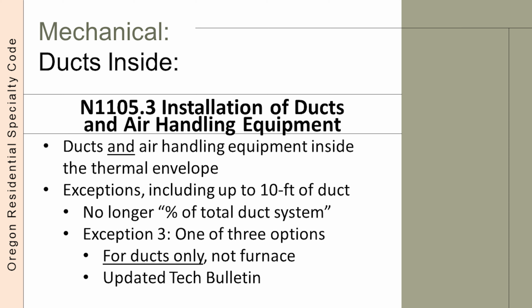Lastly, three options for ducts outside of the thermal envelope that exceed the 10-foot limit are covered in sections N1105.3.1 through N1105.3.3. Customers taking these exceptions and having more than 10 feet of ductwork outside the thermal envelope have to select two additional measures from Table N1101.1(2). If you haven't reviewed it by now, I suggest reviewing the updated technical bulletin covering the buried duct topics. It will help with the next few slides.